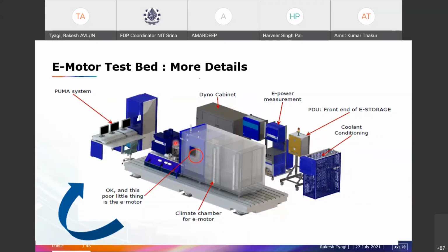This is the dyno cabinet, power cabinet. These are the trolleys where your e-power measurement is done. So we get voltage signals here going to the automation system. Then this is the power distribution unit, for how to connect coolant conditioning. We've discussed that based on requirement, this is done. In case of motor and inverter, there are different combinations possible. Let's say there may be a conditioning unit for the e-motor, controlling the temperature always at 50 degrees.